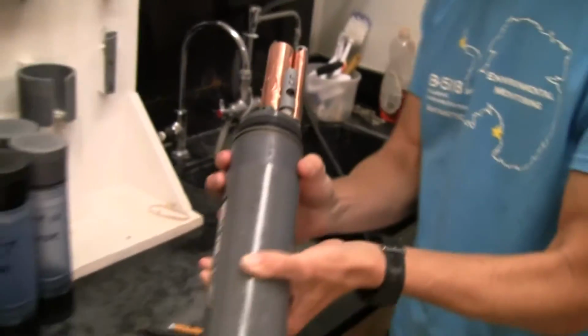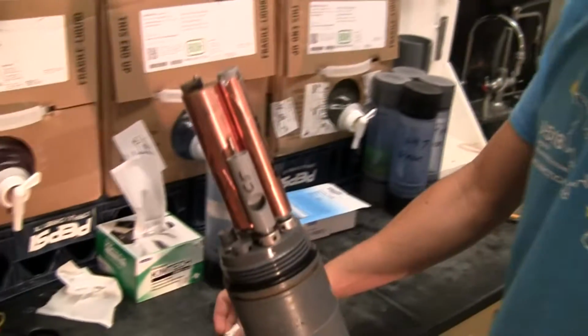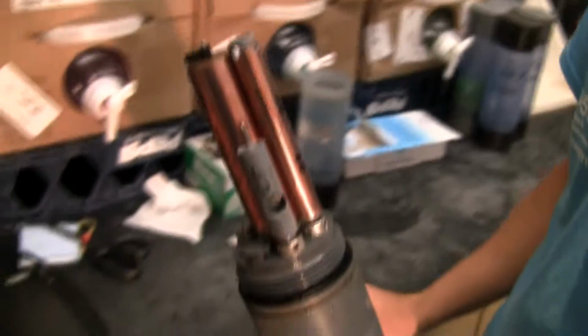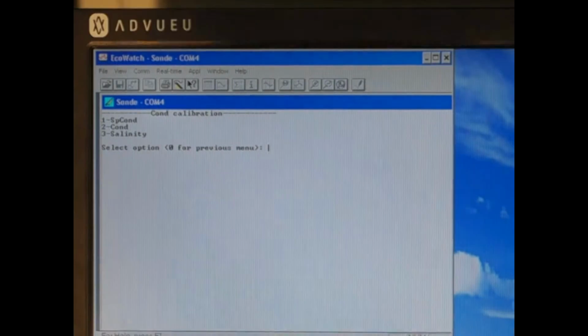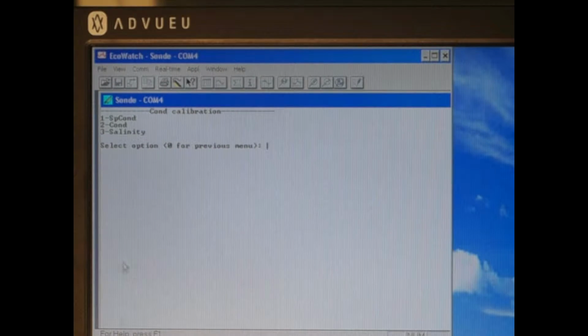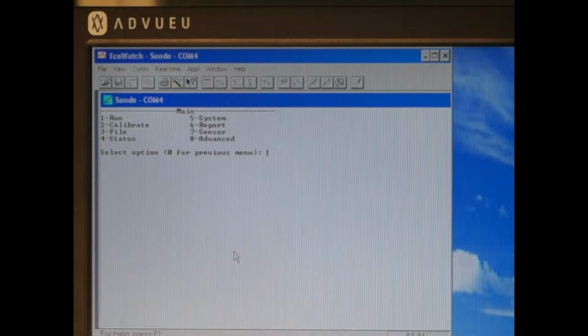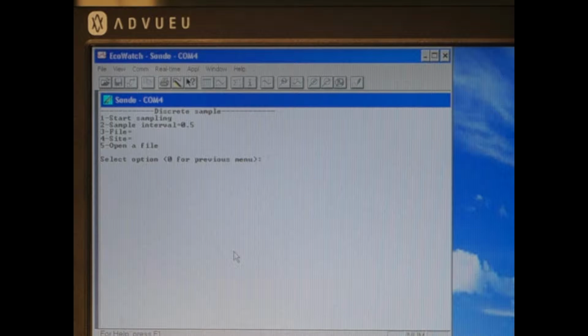Now we're ready to do the zero check on the conductivity sensor. For this, we go back to the computer with the sensor in the air. For the zero check, we do not do calibrate. We actually go back to run. So I'm going to push 0, 0, and then I'm going to go run and discrete sample. Start sampling.